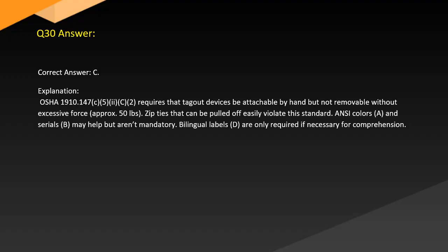Answer. Correct answer: C. Explanation. OSHA 1910.147 C5 requires that tagout devices be attachable by hand but not removable without excessive force, approximately 50 pounds. Zip ties that can be pulled off easily violate this standard. ANSI colors (A) and serials (B) may help but aren't mandatory. Bilingual labels (D) are only required if necessary for comprehension.